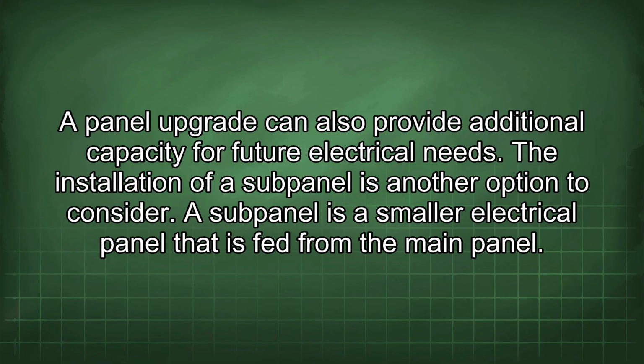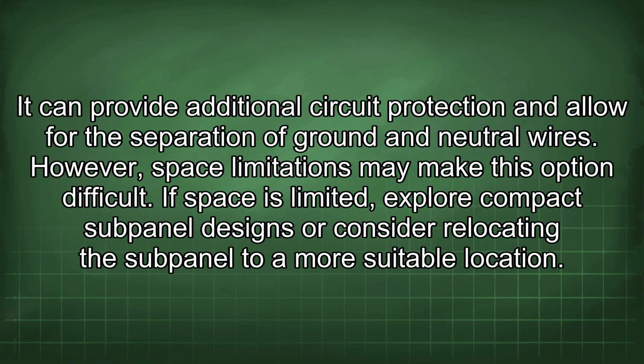The installation of a subpanel is another option to consider. A subpanel is a smaller electrical panel that is fed from the main panel. It can provide additional circuit protection and allow for the separation of ground and neutral wires. However, space limitations may make this option difficult. If space is limited, explore compact subpanel designs or consider relocating the subpanel to a more suitable location.